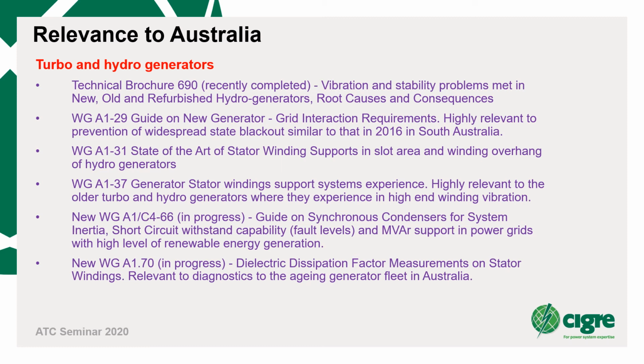The new working group A1.70 just started, covering dielectric dissipation factor measurement of stator windings, relevant to winding diagnostics, particularly for the aging fleet in Australia.